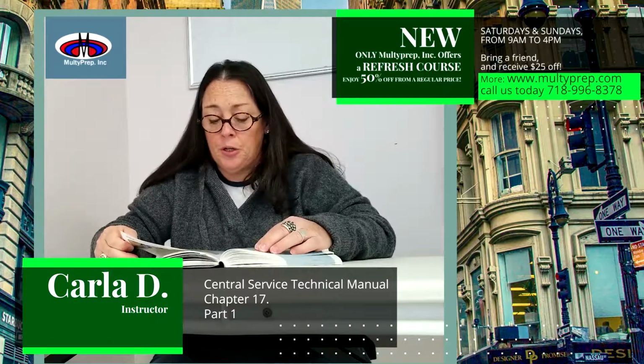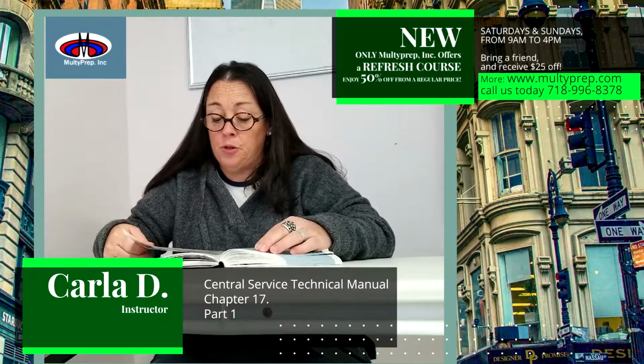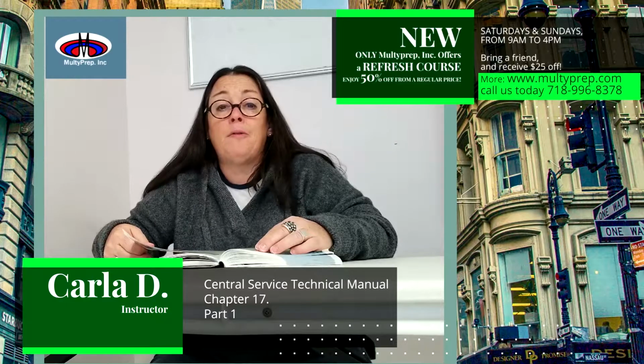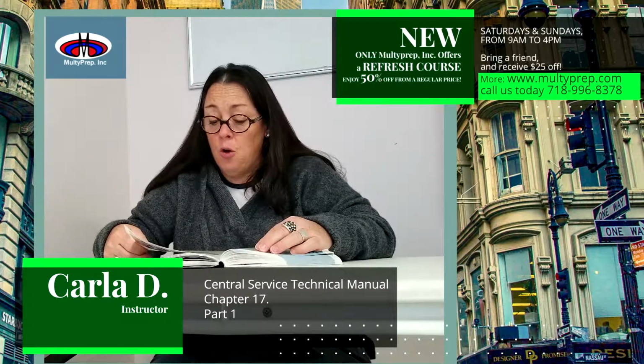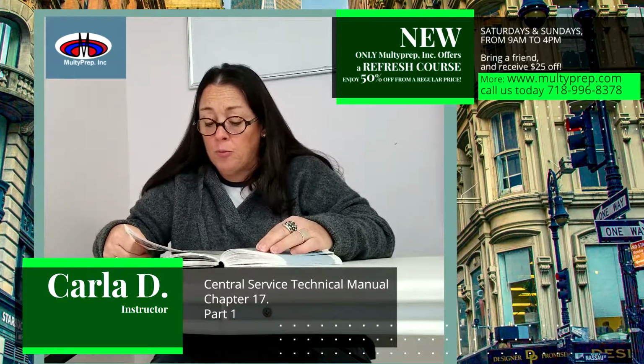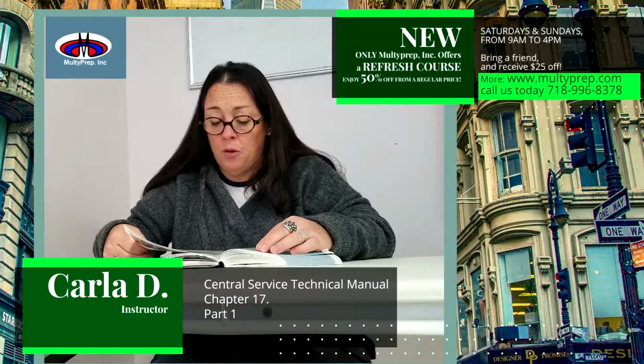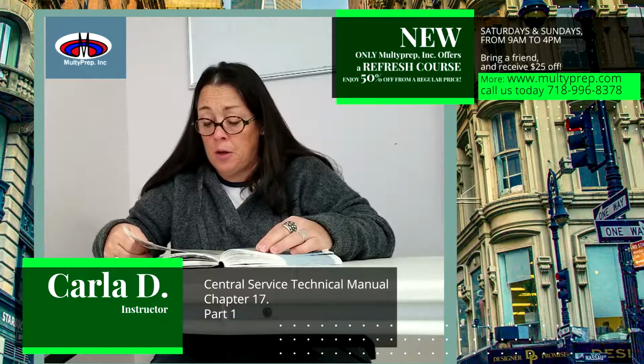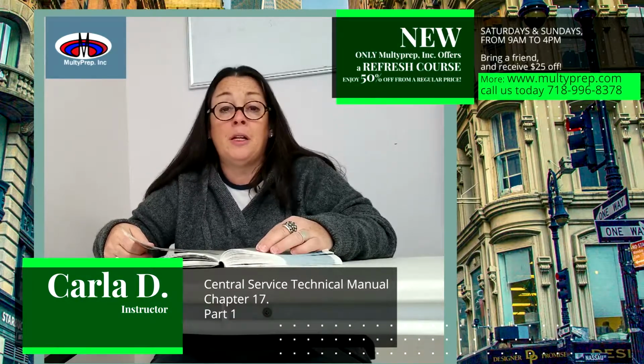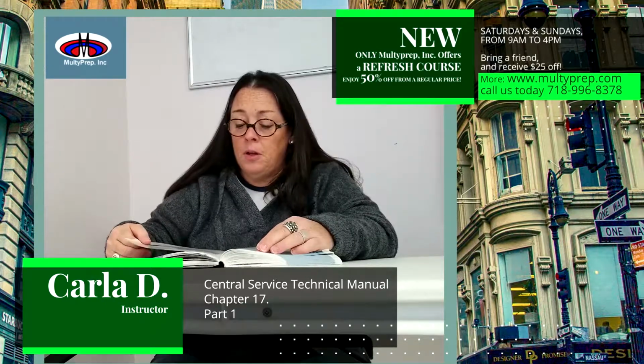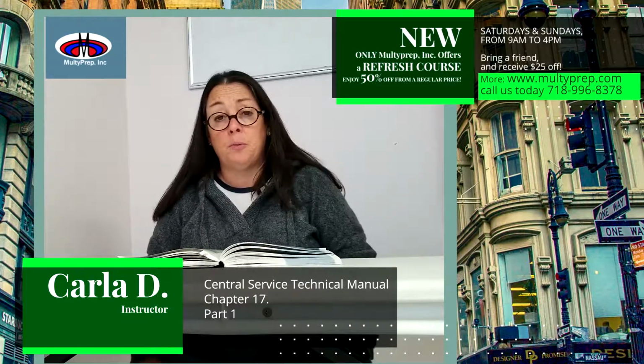If the interpretation of the CI in a package, tray, or container suggests inadequate sterilant penetration, the contents cannot be used and should be returned to the CS department for investigation. Note: it is possible to have one or more unacceptable indicators in a load because of improper packaging or loading, with the remainder of the load acceptable. CIs showing a failing result should require further investigation to determine the cause.